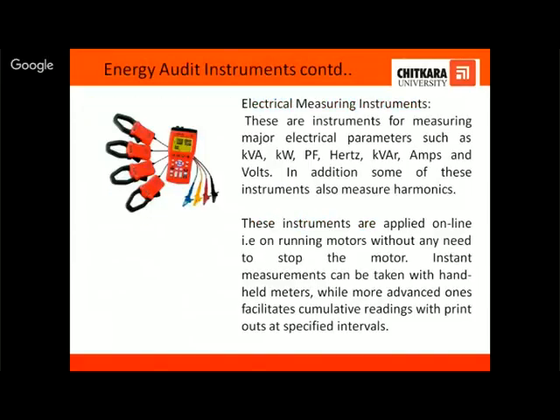So I have just listed a few of the instruments, but I have given a link where you can get all the details of all energy audit instruments. It's a simple power analyzer. Again, it comes in the range of starting from 20-30,000 to the lakhs, but it all depends on what current ratings and what details you need. Do you need a data logger, or don't you need a data logger? These are the instruments which can be put on an online system. We don't need to stop the motor. They directly take the readings online.